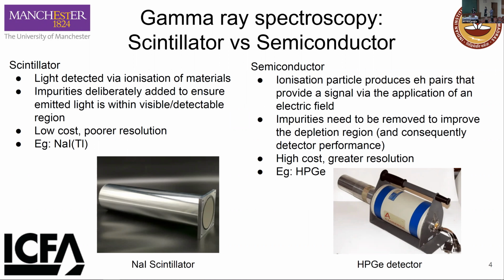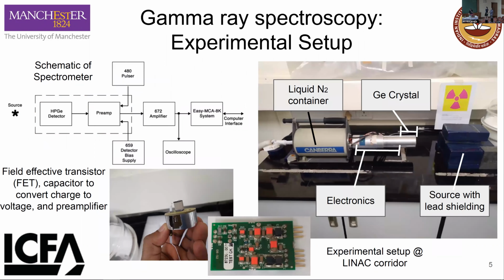They're generally quite low cost, but have a poor resolution when compared to semiconductor detectors. Those work in much the same way, but instead of just scintillation light, they work by a reverse bias voltage across the material, producing a region of no free charge, or a depletion region. So when a charged particle passes through it, it creates electron-hole pairs, and consequently produces electrical currents. Unlike scintillator detectors, impurities need to be removed to improve the depletion region within a detector. They have a higher cost, but a greater resolution compared to the scintillators.